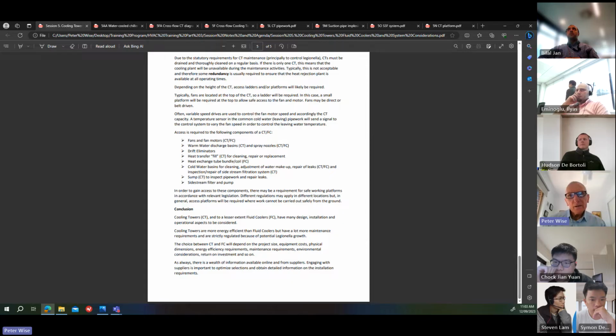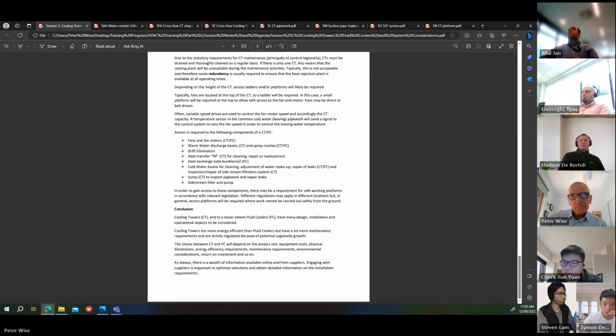So the equaliser line is an ideal spot for Legionella to grow if you have that situation. So what's commonly done is the flow to the side stream filter system is taken from the equalising line. Instead of taking it out of the basin of the cooling tower, you take it out of the equaliser so that you've always got flow through the equaliser, and it goes down through the side stream filtration and back to the sumps. Excuse me. That's something that I haven't mentioned in the notes, but it's something to keep in mind as well. That's the ideal place to get the suction line for the side stream filtration, out of the equaliser. So that's probably your biggest risk.